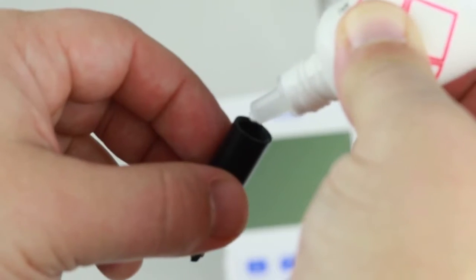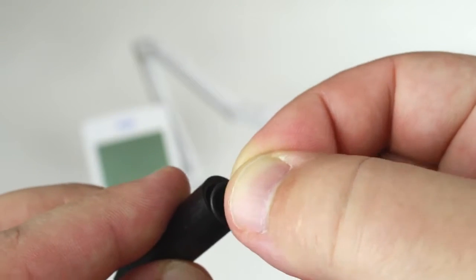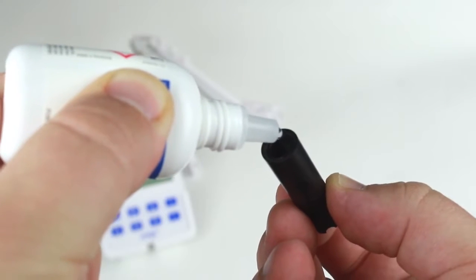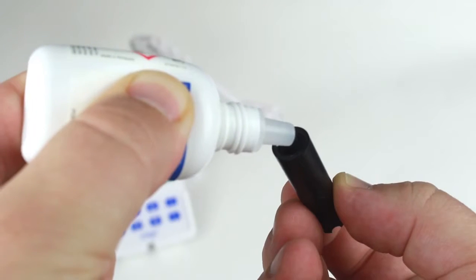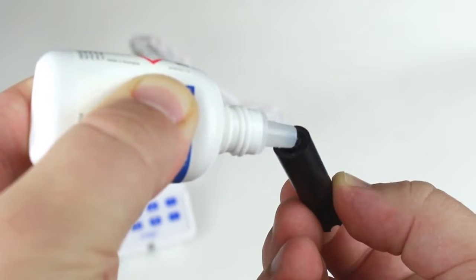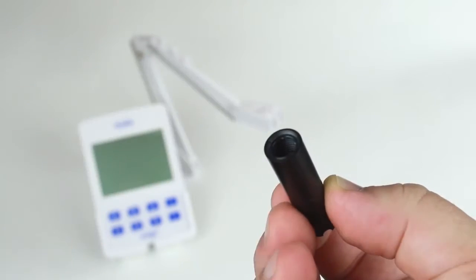Take a dissolved oxygen membrane and O-ring and rinse the membrane with some dissolved oxygen electrolyte. Next, position an O-ring at the bottom of the threading for the membrane cap. Once the O-ring is in place, we can start filling the membrane cap with electrolyte. It's important to fill the cap about 3/4 with electrolyte. Tap on the side of the cap to make sure that any air bubbles rise to the surface.